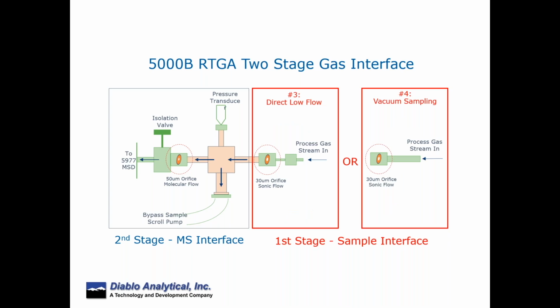The third option for an interface is a direct flow option, and this is if you want to minimize the removal of gas from your process, microreactors, for example. And so you can have a small 16th inch stainless steel line with a flow that's in the maybe 8 mils per minute total flow, and that flow would go through and across the orifice. It would be again drawn in by the bypass sample scroll pump.